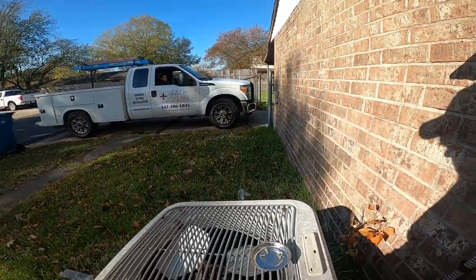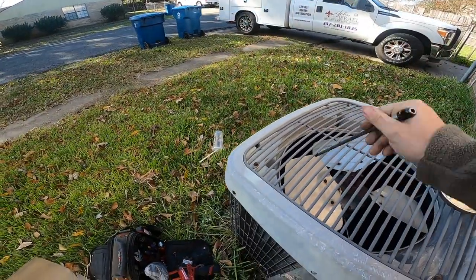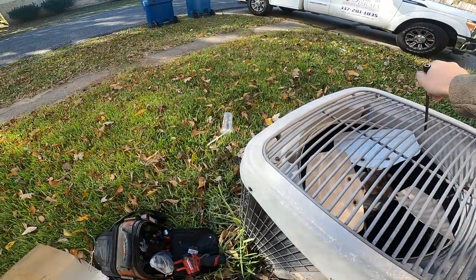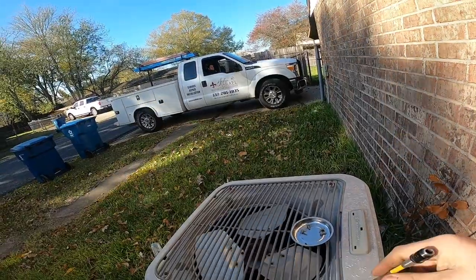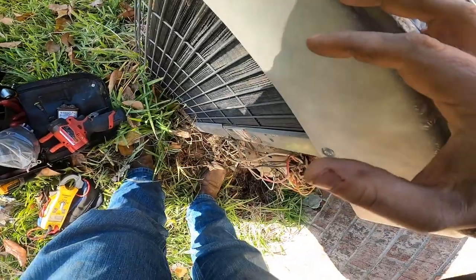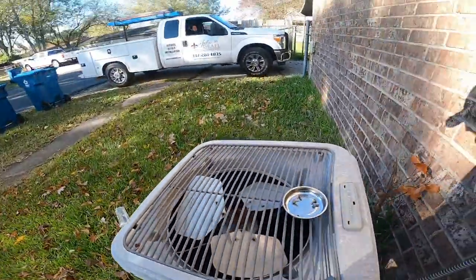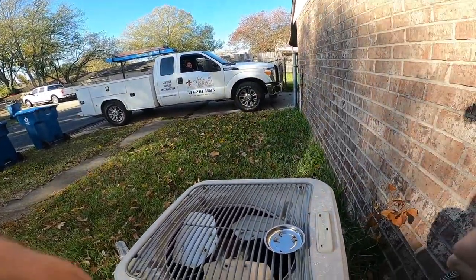So let me call him and let him know. Yeah, see, it's stiff. And I can feel the heat coming off of it. Yep, he's definitely gonna have to have a fan motor on this thing. All right, let me get in touch with him. This is a rental. I gotta get in touch with the landlord.